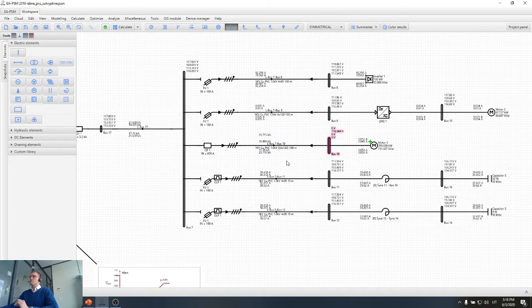So the selectivity principle is to disconnect only those protection devices that are facing failure, that are facing a short circuit or another problem, and we should not disconnect other protection devices that are working in normal mode. This is to ensure that after the disconnection of the protection devices, all the good equipment will still be working. So this is the last principle of the protection coordination in electrical networks.